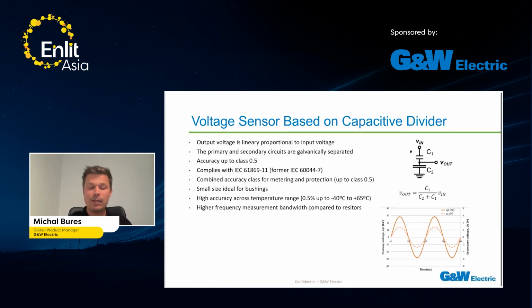Our sensors, as I mentioned, are based on capacitive dividers. The output voltage is linearly proportional to the input voltage, so it's simply a divider. The primary and secondary circuits are galvanically separated. Accuracy class for the standard portfolio is 0.5. It complies with the newest IEC standard, and we are part of the IEC committee. We are also working on the new standard, which will be released in the following years. You have, as I mentioned, a combined accuracy class for metering and protection, so you can measure both at the same time. You can achieve small sizes, which are ideal for bushings. Thanks to the capacitive divider, you have high accuracy and a temperature range from -40 degrees Celsius to +65 degrees Celsius. And as I mentioned, you have a higher frequency measurement bandwidth compared to resistive dividers.